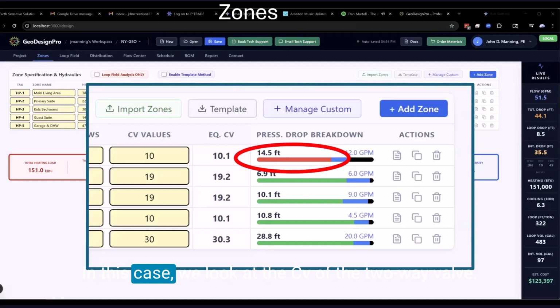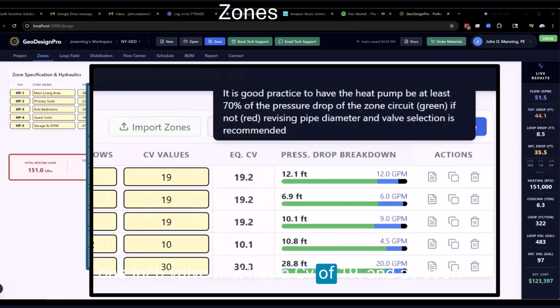In this case, we look at the CV of the two-way valve. This particular heat pump operates at 12 GPM. We got a CV of 10. My rule of thumb is I'd like to get close to twice the flow rate. Now, there's a particular valve I like, a Belimo 1-inch valve that has a CV of 19. And as soon as I change that CV value from 10 to 19, the heat pump becomes over 70% of the total pressure drop. So it's a guide to give you feedback in selecting parts that you do have control of.